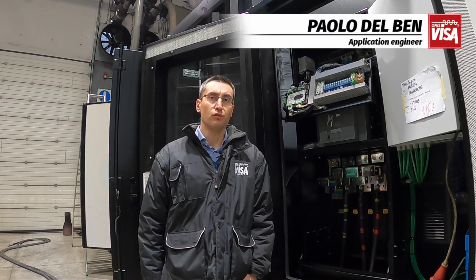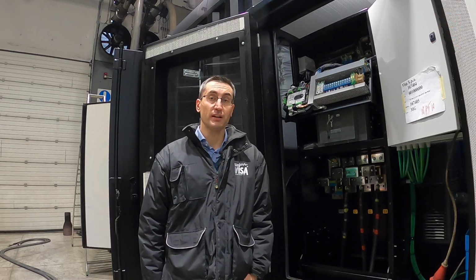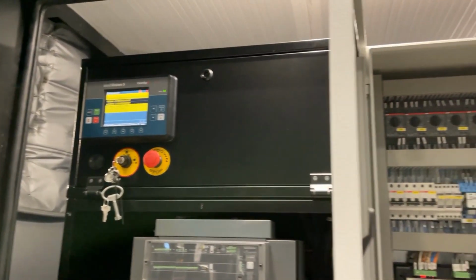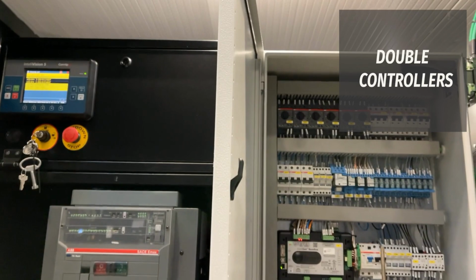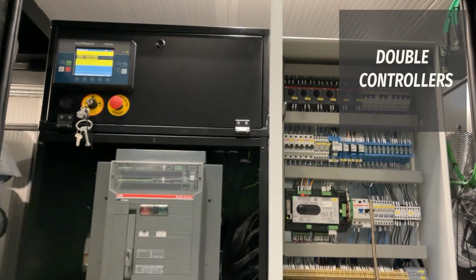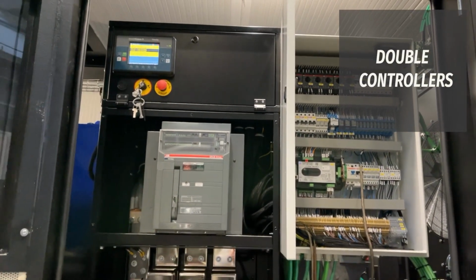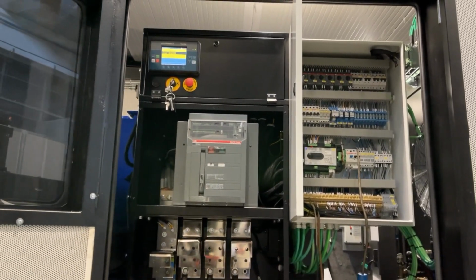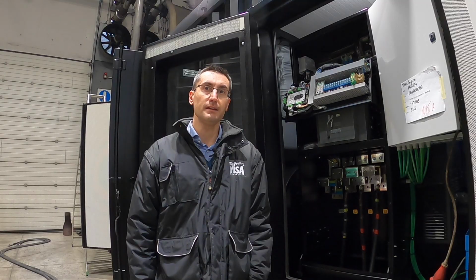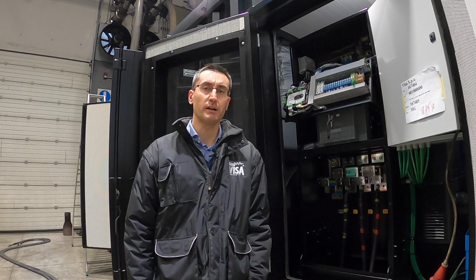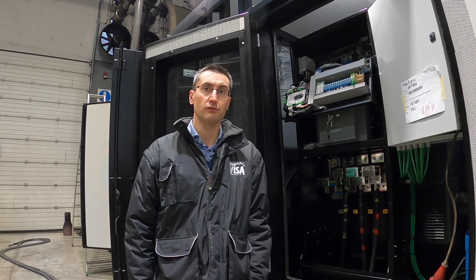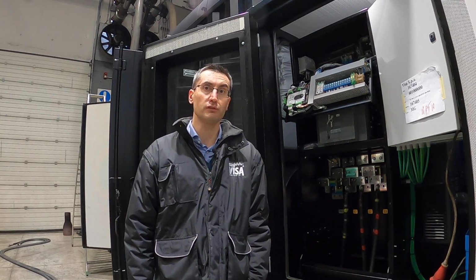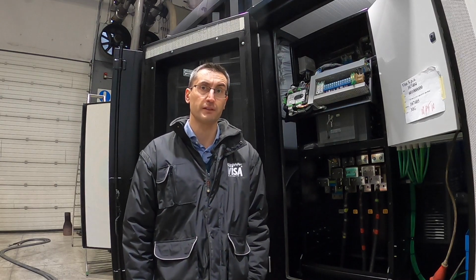Basically, in each genset, the two controllers work simultaneously and share a signal called heartbeat. In standard operation, the secondary controller is inhibited as long as the primary is up and running. On the other hand, in case of a failure of the primary controller, the secondary controller is able to take full control of the genset in only a fraction of a second.